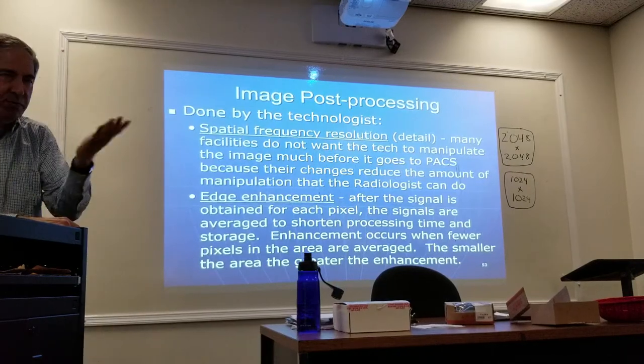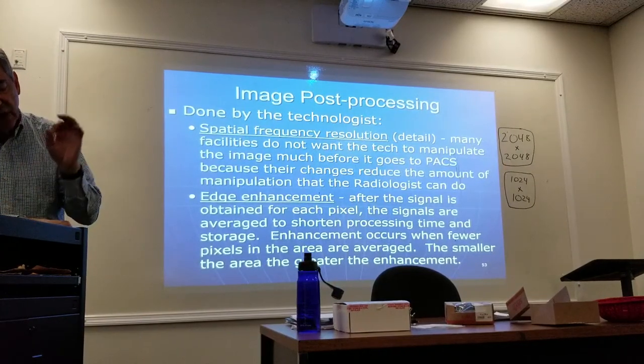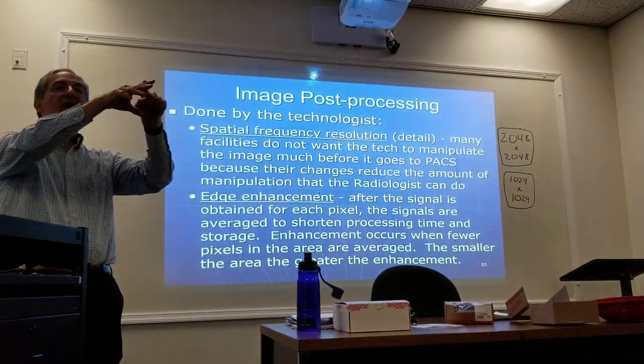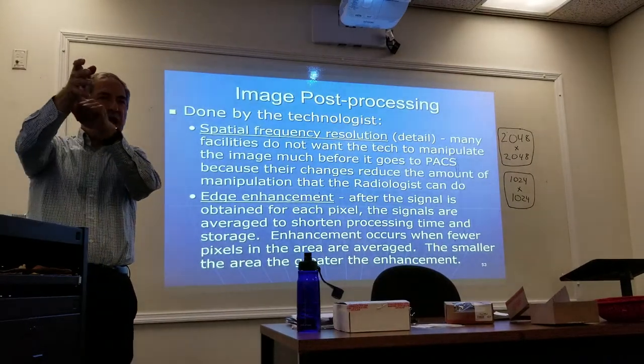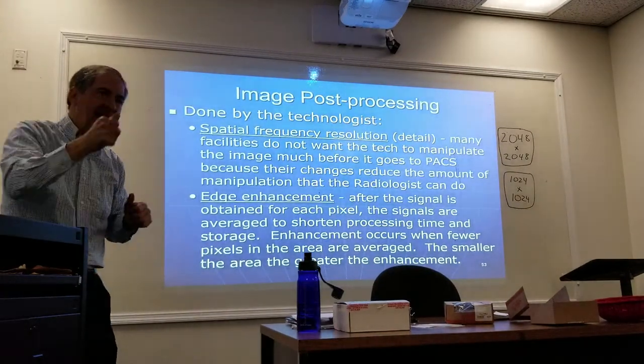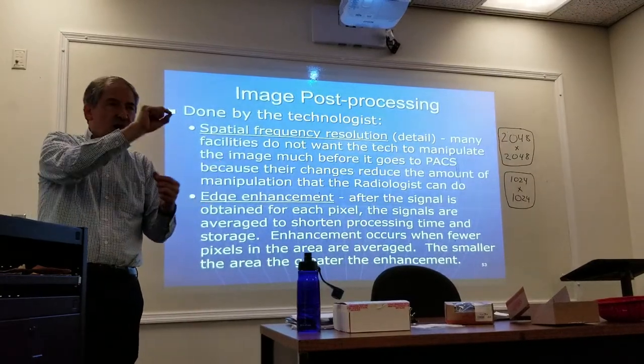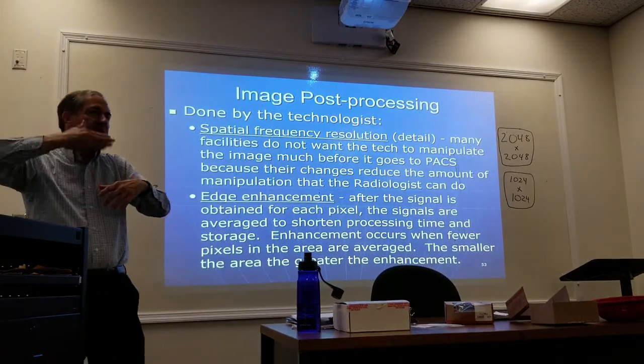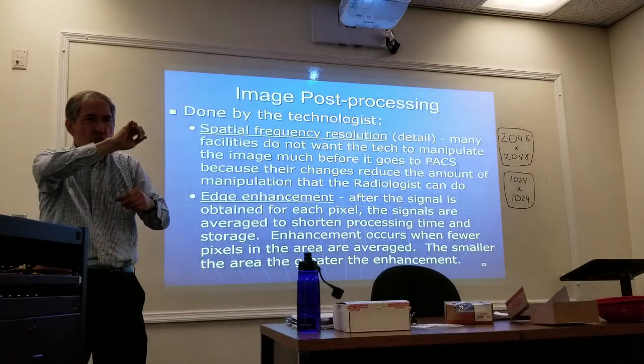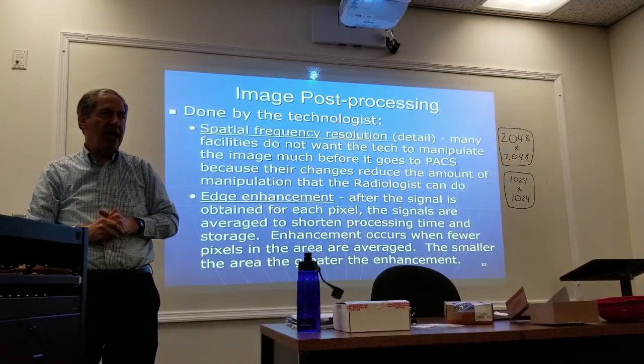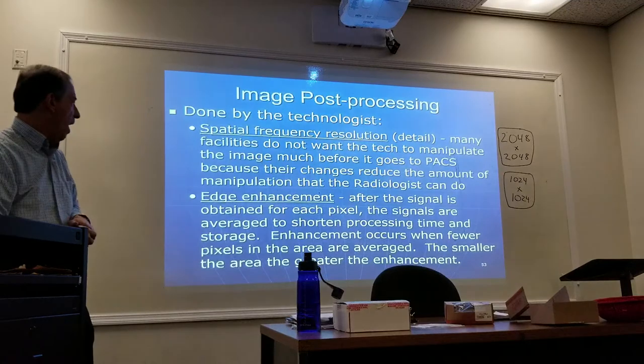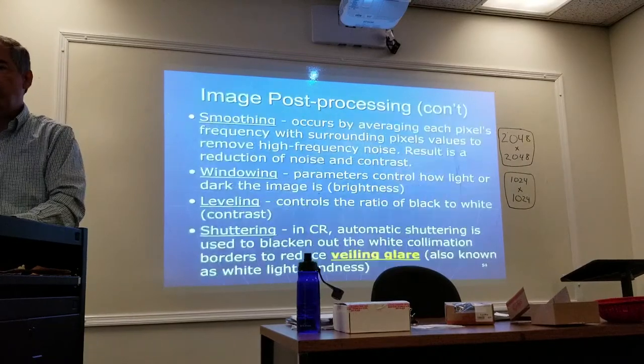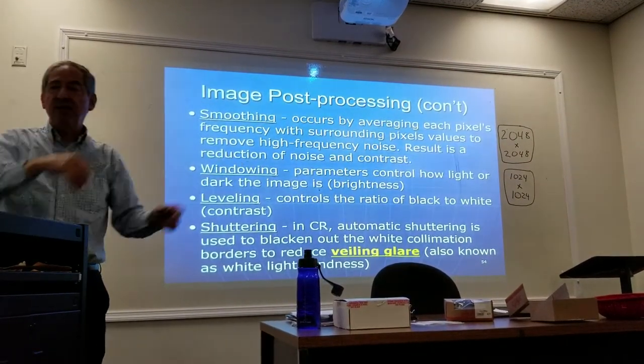Edge enhancement is used a lot with a C-arm. After the signal is obtained, the signals are averaged — fewer pixels in a small area gives greater enhancement. Basically, you can hit a button on the C-arm to give greater detail to extremity fractures along the edge of a bone. If you're doing a hand or wrist and want to see a fracture along the edge, edge enhancement makes it more grainy but you can see that fine detail.